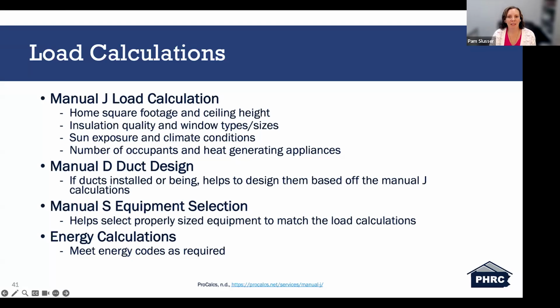Then we move on to the Manual S, equipment selection. This next step matches the calculated loads from Manual J with real manufacturer equipment data. So this step ensures that the heat pump or HVAC unit is sized correctly based off the calculations. And then you have energy calculations. Finally, at the end, many energy codes, including the Pennsylvania UCC, require proof of compliance through energy calculations. These include verifying that the building envelope and mechanical system meet minimum energy or efficiency standards. So that's looking at all the ratings that we had talked about prior.